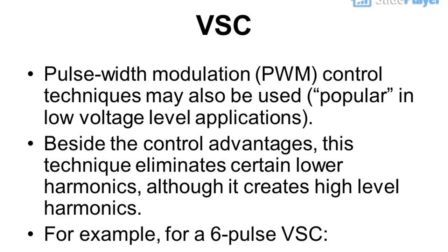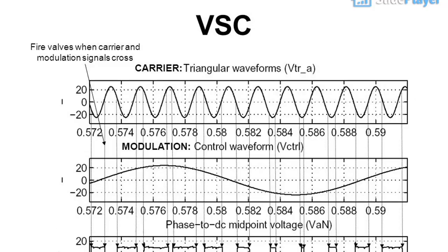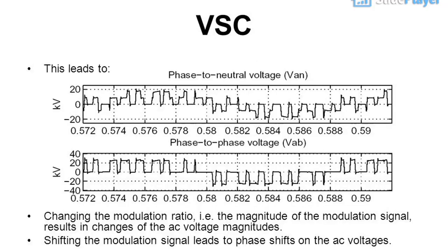For example, for a 6-pulse VSC, fire valves when carrier and modulation signals cross. This leads to: changing the modulation ratio, i.e., the magnitude of the modulation signal, results in changes of the AC voltage magnitudes. Shifting the modulation signal leads to phase shifts on the AC voltages.